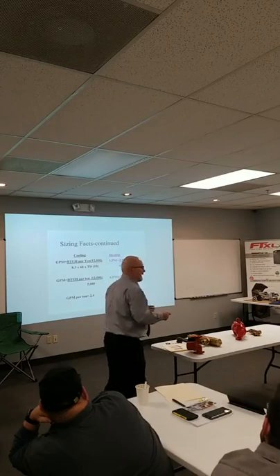So if I have a 200,000 BTU boiler and I want to distribute 200,000 BTUs, what do I need? I need a pump to do 20 gallons a minute. That's how simple it is to figure out what pump you need. This equation, GPM is equal to BTUs divided by 10,000 at a 20 degree delta T. But if we're going to change the delta T, then we have to change this number down at the bottom.